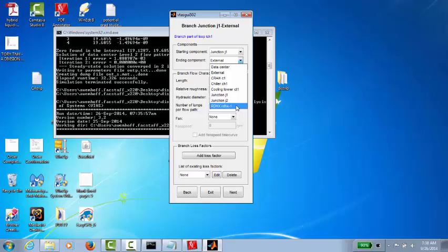What we did in the data center block is we said that the first row implemented a rear door heat exchanger of type RDHX1. So this allows you to have multiple rear door heat exchangers of the same type in the data center without having to define each of them individually. What VTAS does by default is it'll name the placed rear door heat exchanger with the dash in it. So here, our placed rear door heat exchanger is RDHX-1. So we're connecting then the chilled water loop up to this placed rear door heat exchanger inside the system.